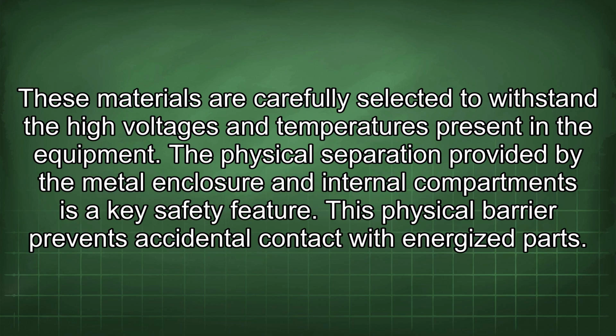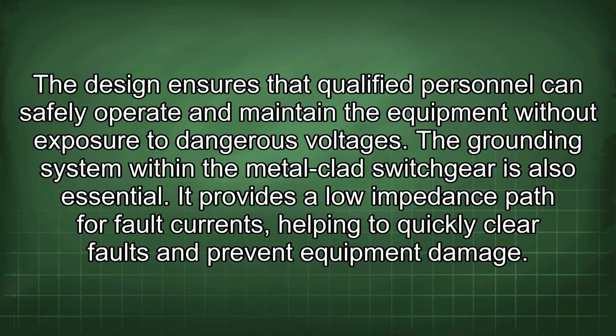The physical separation provided by the metal enclosure and internal compartments is a key safety feature. This physical barrier prevents accidental contact with energized parts. The design ensures that qualified personnel can safely operate and maintain the equipment without exposure to dangerous voltages. The grounding system within the metal-clad switchgear is also essential. It provides a low impedance path for fault currents, helping to quickly clear faults and prevent equipment damage.